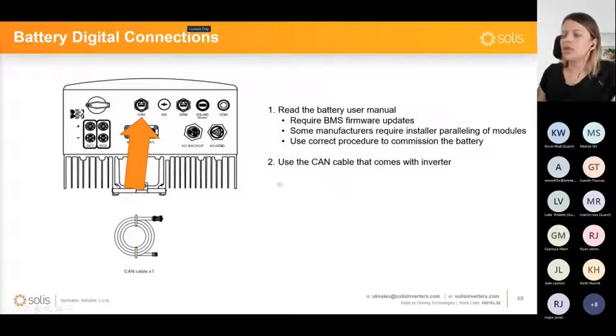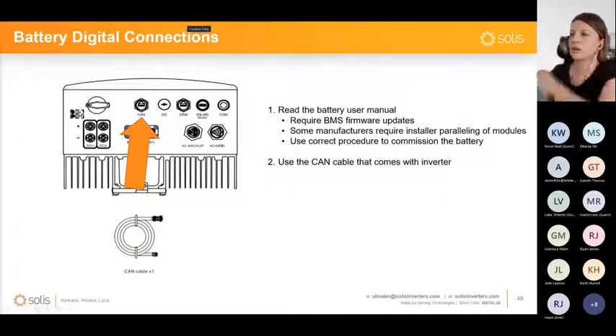As for the CAN communication cable, it's always best to use the one that comes with the inverter. That's just a straight cable. Nothing fancy about it, but we did have some troubles. For example, with Pylontech, at some point they started providing their communication cables with the batteries, but those connections were not straight. A few of the pins were reversed, and the cables were not working properly. They were not sending data.